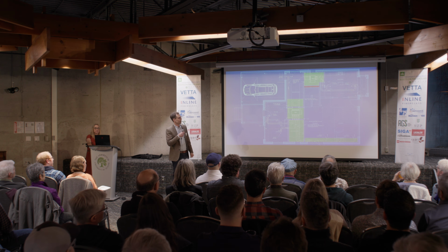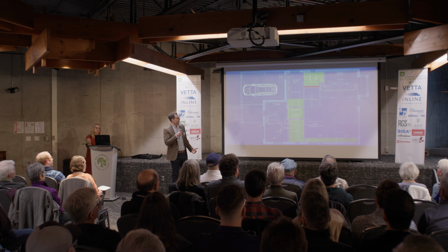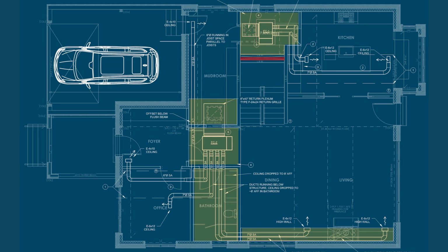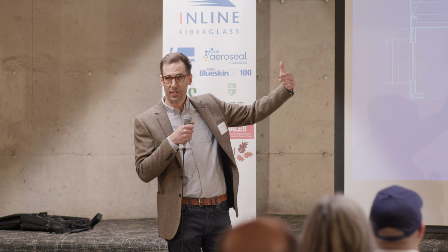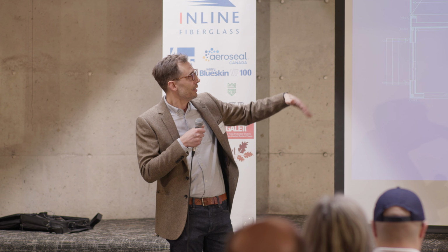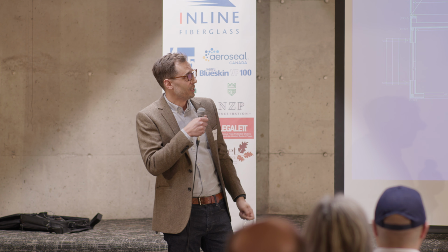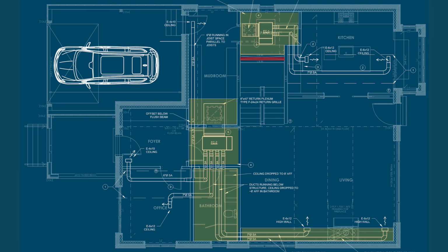So now, as far as the architectural impact goes, the house was built with 9-foot ceilings. So here you see the ground floor plan. Anything that's shaded has been dropped deliberately to 8 feet to accommodate the system. So it is a fan coil system. We're delivering water, either hot or chilled water, to these fan coils, and then it transfers to air and runs out to the spaces. So the one at the top of the screen is in the pantry. We have a removable ceiling in there to be able to access and maintain that unit over its life.